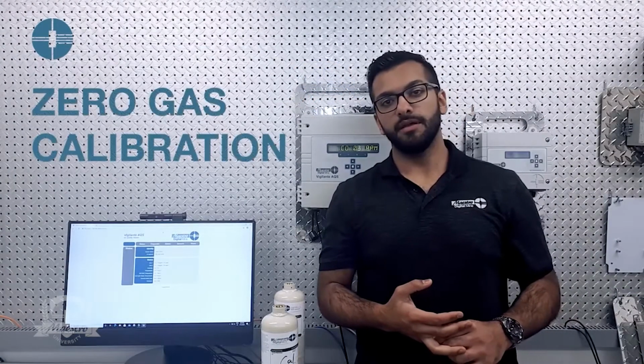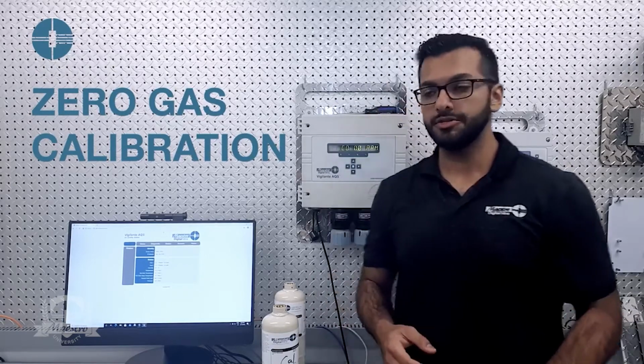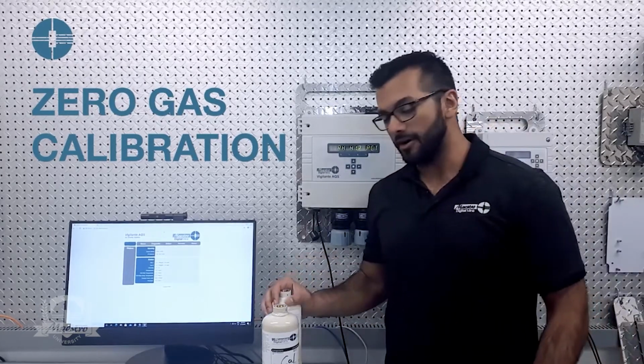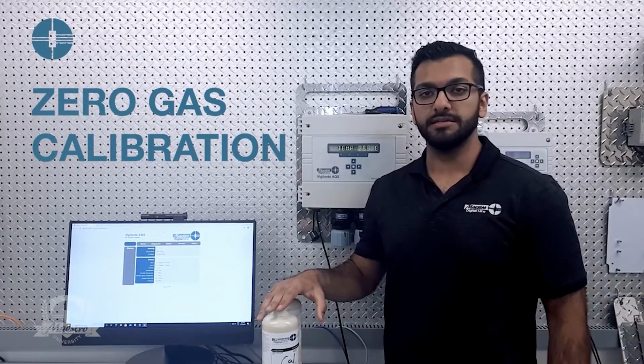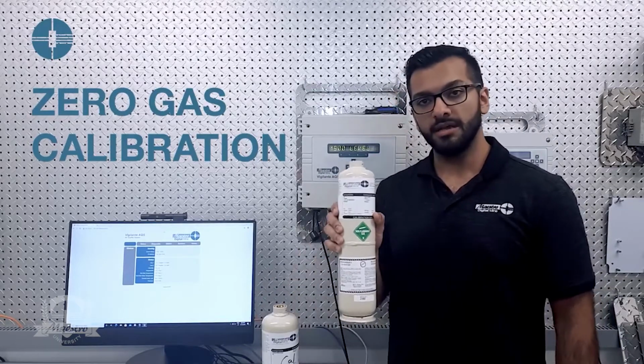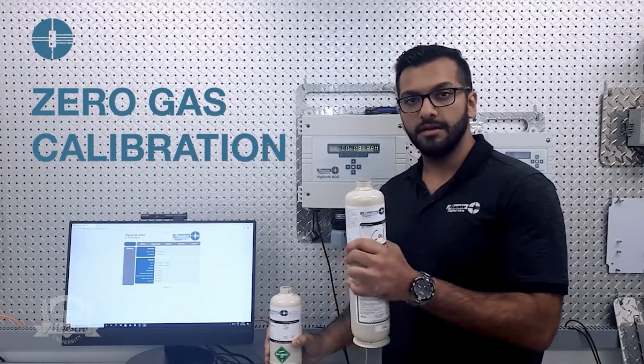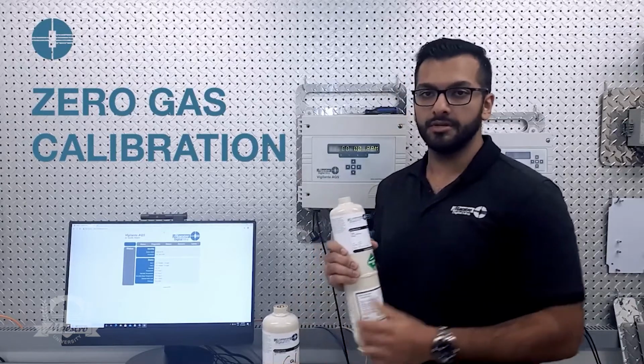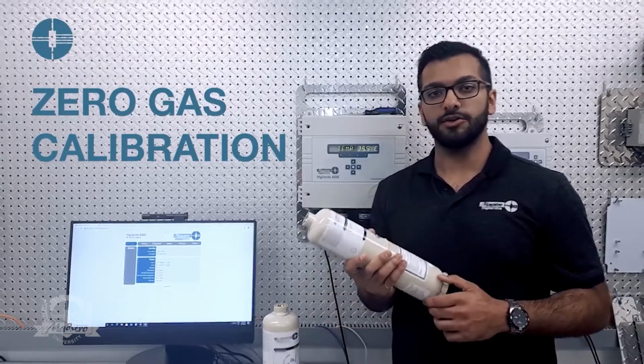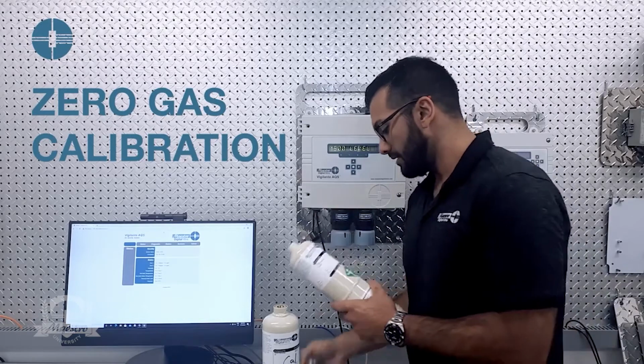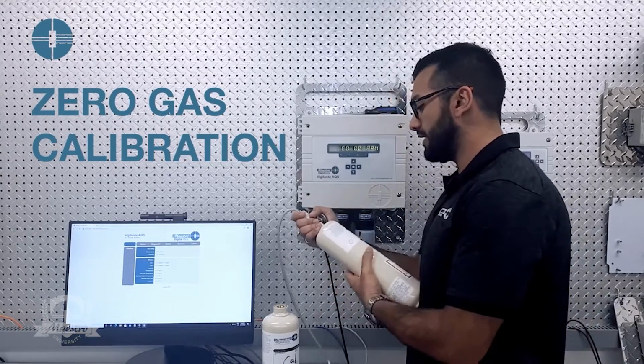So the next step is calibrating your gas sensors. And as mentioned before in our checklist, we have two gases. One is our zero gas and the other one is our span gas. So to calibrate a sensor, we start with the zero gas first. So I'm just gonna connect the regulator here.